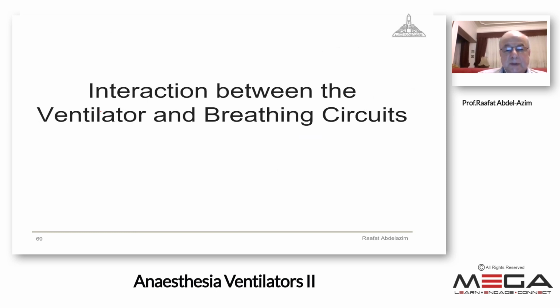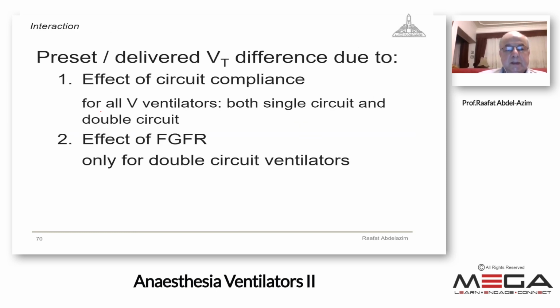The interaction between the ventilator and the breathing circuits appears as a difference between the preset and the delivered tidal volume. Of course, we adjust the preset tidal volume according to the body weight of the patient. For example, if the preset tidal volume is 500, but what is given actually to the patient will differ according to two factors. The first one is the effect of circuit compliance that will lead to loss of part of the preset tidal volume. So the delivered tidal volume will be less than the preset.